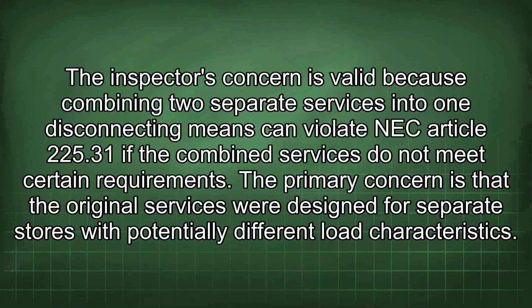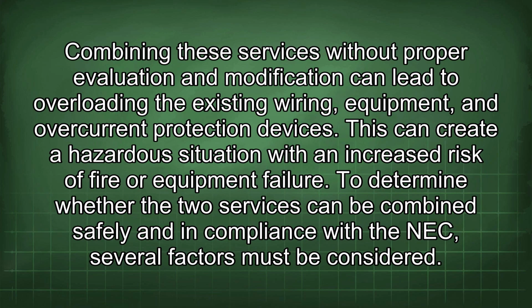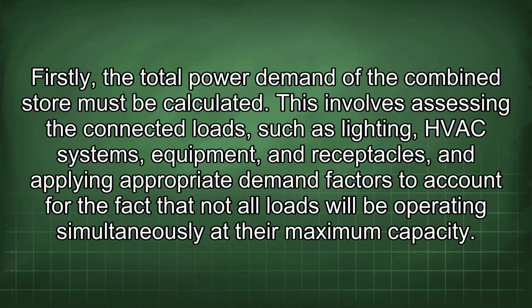The primary concern is that the original services were designed for separate stores with potentially different load characteristics. Combining these services without proper evaluation and modification can lead to overloading the existing wiring, equipment, and overcurrent protection devices. This can create a hazardous situation with an increased risk of fire or equipment failure. To determine whether the 2 services can be combined safely and in compliance with the NEC, several factors must be considered. Firstly, the total power demand of the combined store must be calculated.